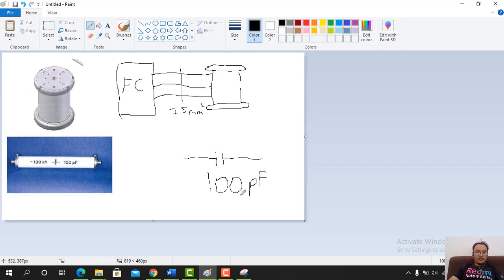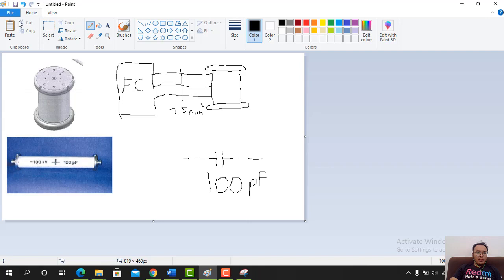This measuring capacitor will be connected between the grounding switch's secondary device, and at the top of the measuring capacitor will be placed the connection card that connects between the measuring capacitor and our test transformer. Okay, next I will clear this.